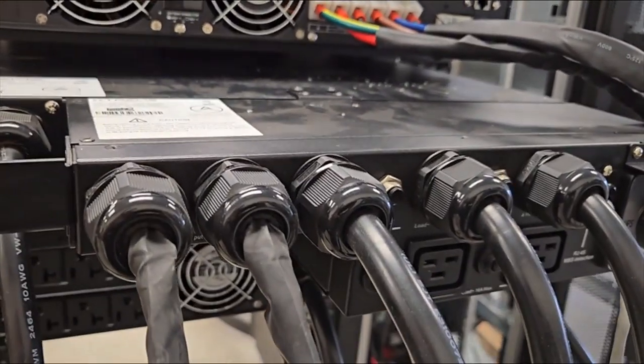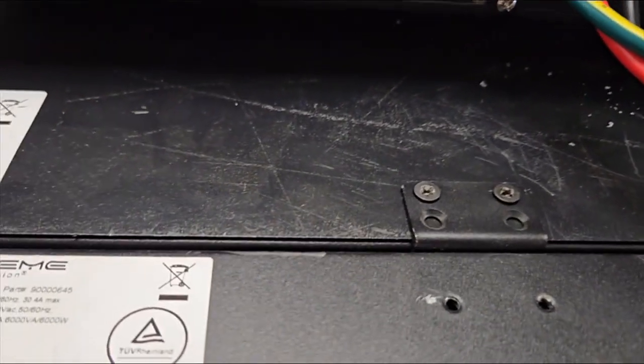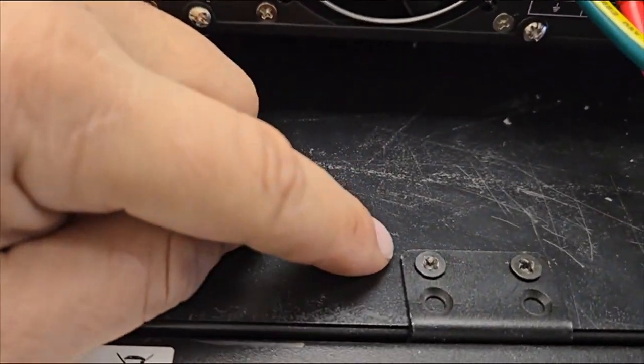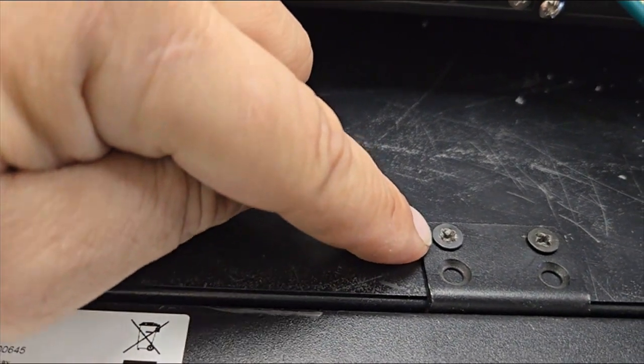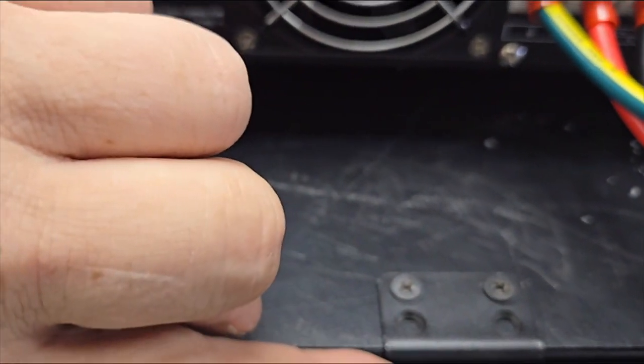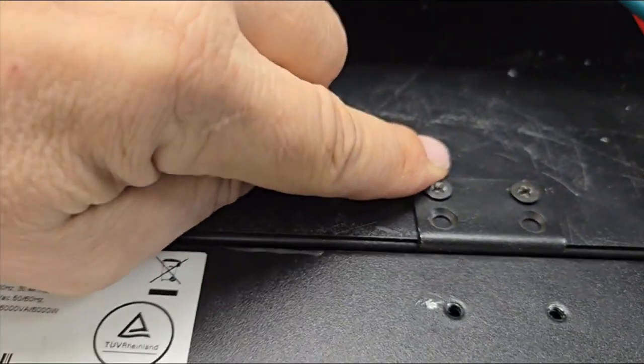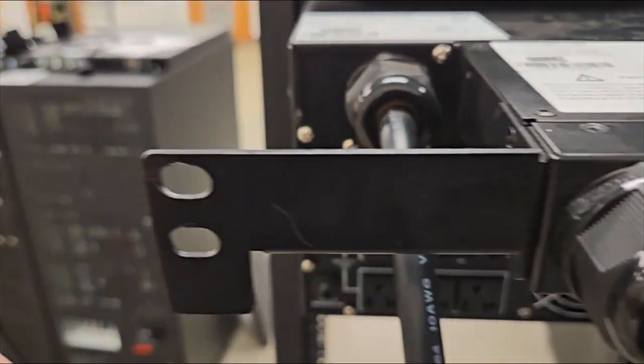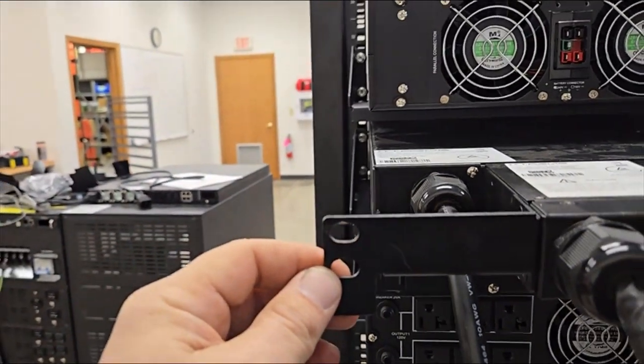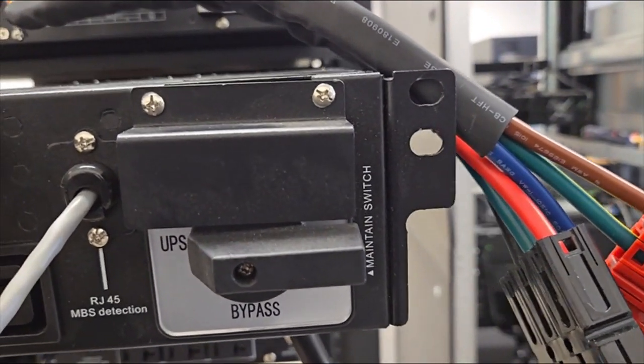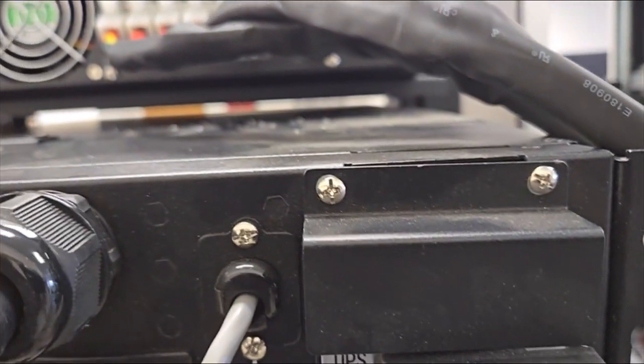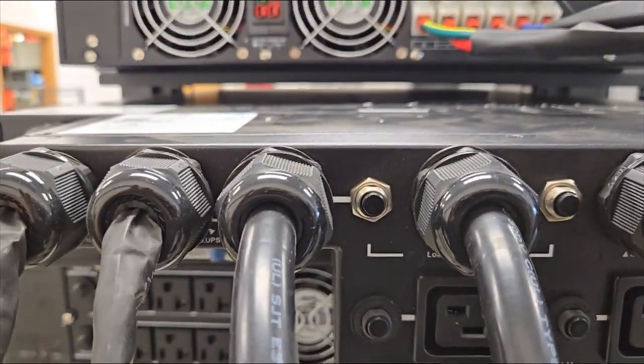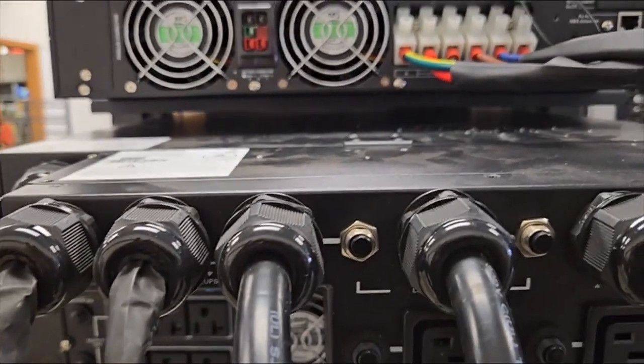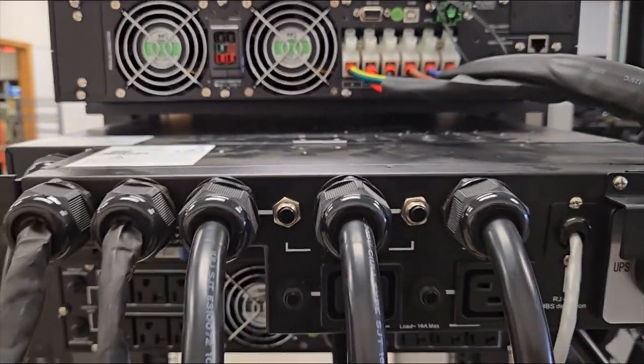Mounting the XBDM to the battery module. The XBDM comes with two brackets. The battery module has two screw holes in this angled bracket that screws into the back of the XBDM and then into the cabinet. It also comes with a standard 19-inch rack rail kit that could be an option as well to zero-U mount the XBDM behind the battery or UPS module, depending on the depth of the enclosure.